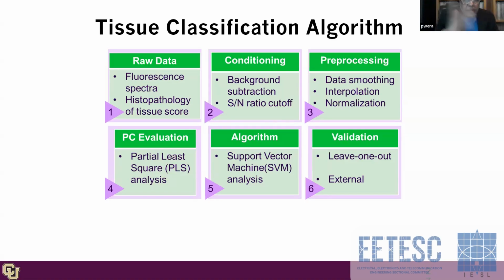So we had to do a background subtraction. Remember, I told you when the needle is inside the body, that separation between the benign and the malignant is very small. So if the noise floor is very high, that signal begins to get even smaller. So you do a background subtraction, then we decide on a signal to noise level. And if the signal to noise level of that particular signal somehow doesn't meet the requirements, we just take it out because it is already corrupted.